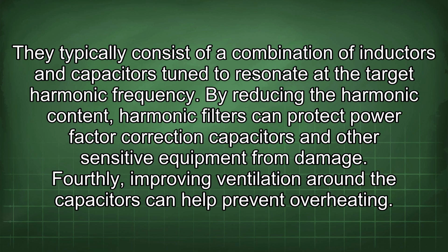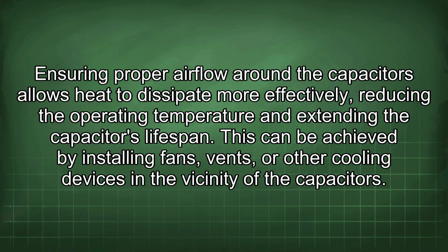Fourthly, improving ventilation around the capacitors can help prevent overheating. Ensuring proper airflow around the capacitors allows heat to dissipate more effectively, reducing the operating temperature and extending the capacitor's lifespan. This can be achieved by installing fans, vents, or other cooling devices in the vicinity of the capacitors.